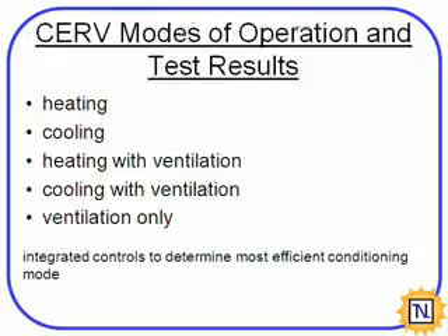We'll be taking a look here then at the modes of operation and some initial test results of the system. The modes are heating, cooling, heating with ventilation, so pulling fresh air inside, heating that air, and then using it to condition the space. Cooling with ventilation, as well as ventilation only, which is either ventilation or dehumidification. And so an important feature then is that these controls, as I was saying earlier, need to be smarter in dealing with all these different cases. So it needs to know how to switch between these different modes and which mode is the most efficient to be operating.